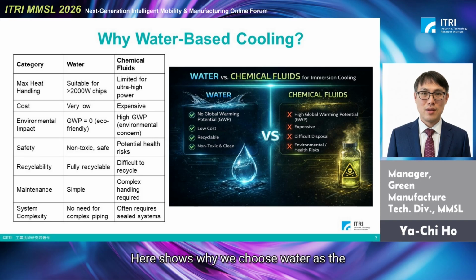Here shows why we choose water as the cooling fluid. We compare water with chemical fluids in several important areas. First, water has much better cooling performance. It can handle very high heat, including chips over 2,000 watts. Chemical fluids, on the other hand, are limited when the heat is too high. This makes water a better choice for future AI and high-power systems.